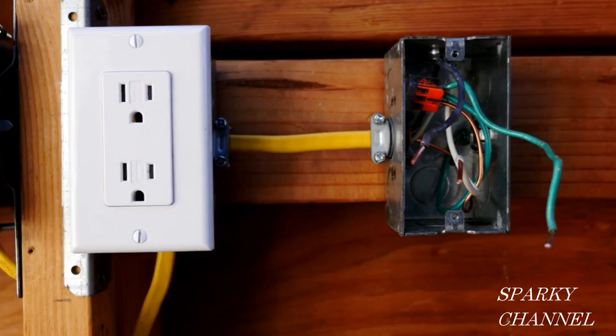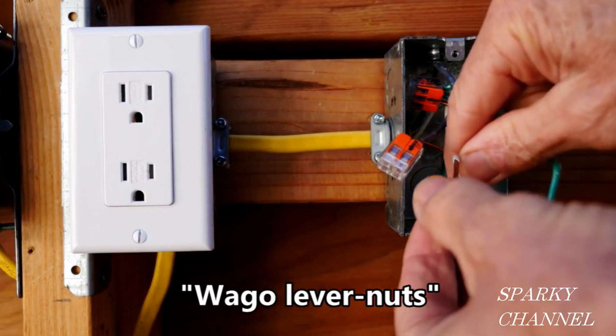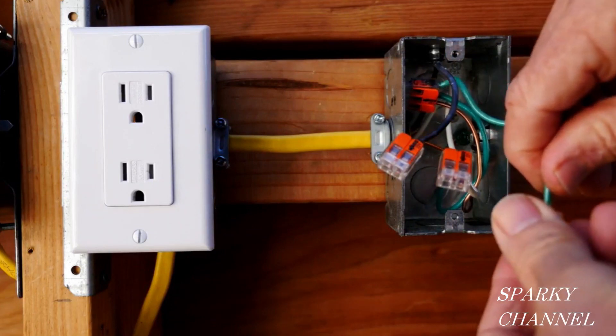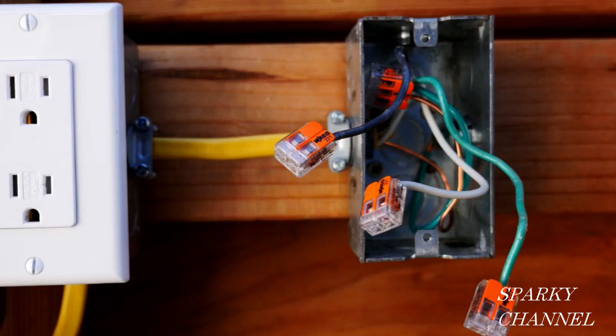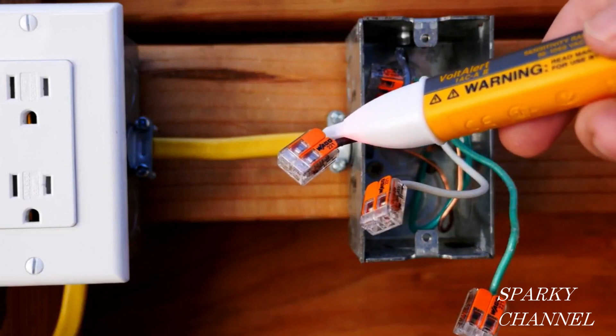So I'm going to show you how to identify which is the hot and which is the neutral. What I'm going to do — and of course the electricity is off — I'm going to put these, called Wago lever-nuts, on the ends of the wires for safety. I'm going to temporarily turn on the electricity and make a test to determine which is the hot and which is the neutral. I have temporarily turned back on the circuit breaker, put the Wago lever-nuts on all of the wires for safety, and I'm using my voltage detector to test all the wires. And this is your hot wire right here.